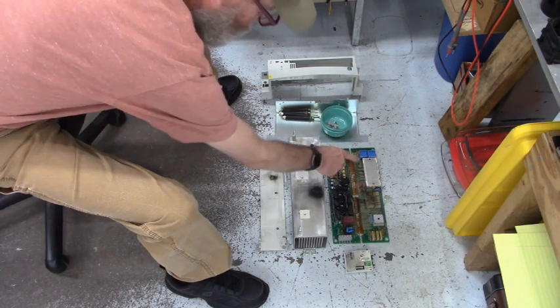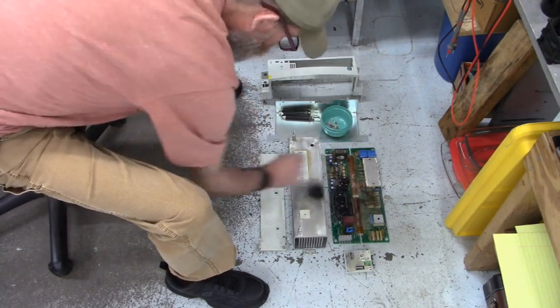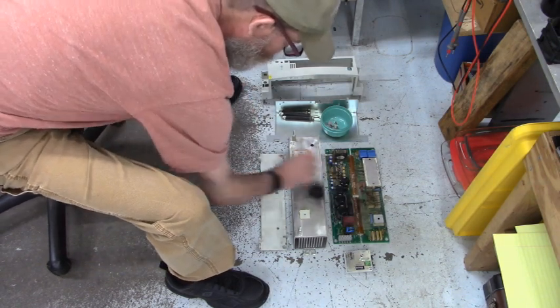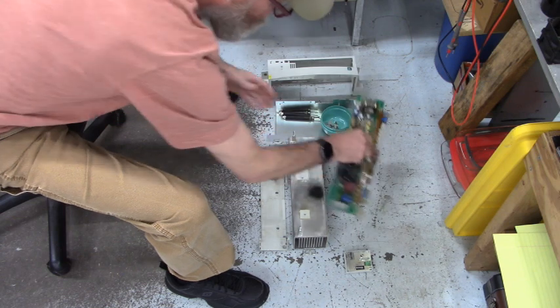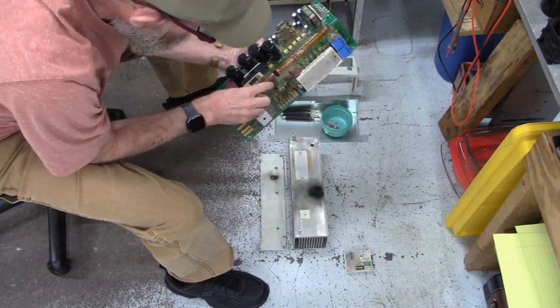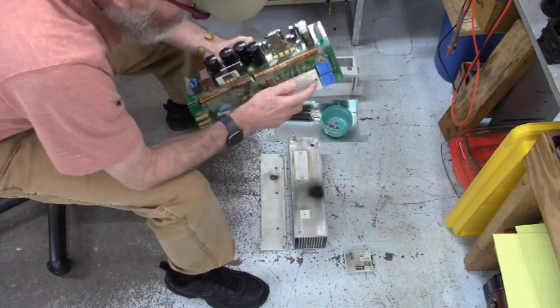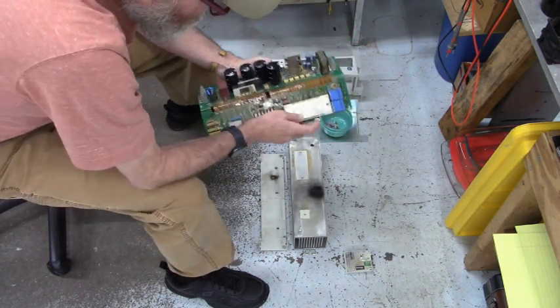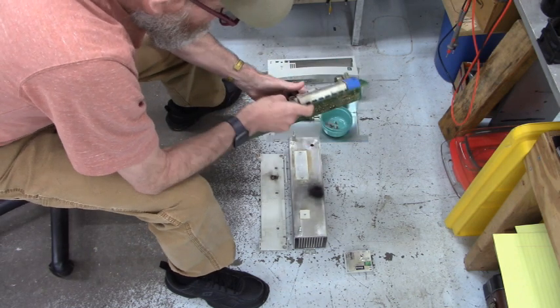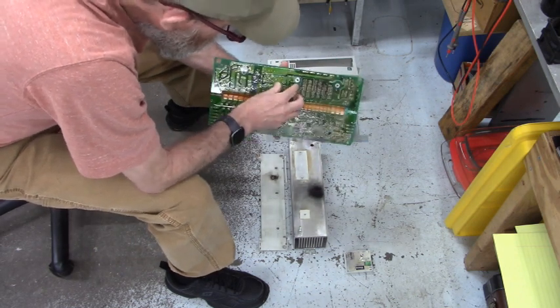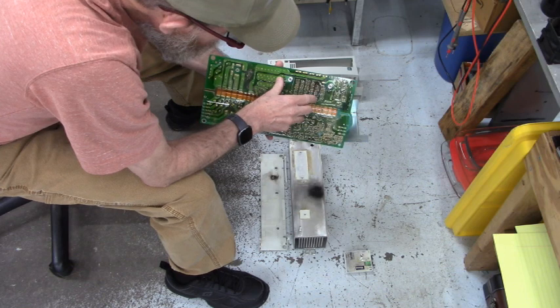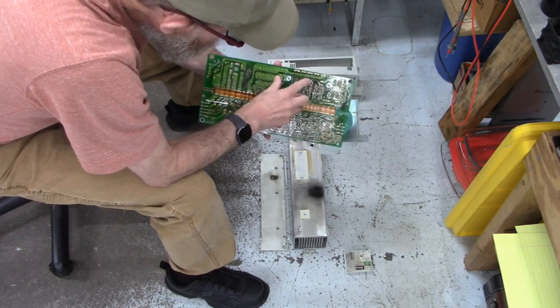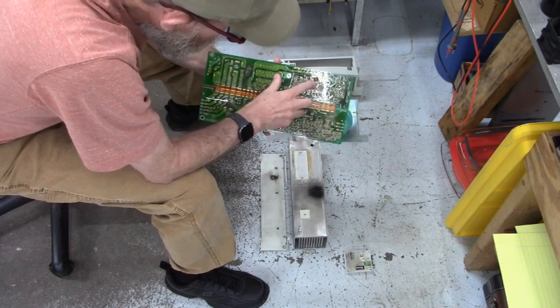This is from the IGBT and this over here looks like it's in the area of this flexible ribbon cable. Now the IGBT is blown out and when that flamed out it wiped out all of these devices in these firing channels right here.